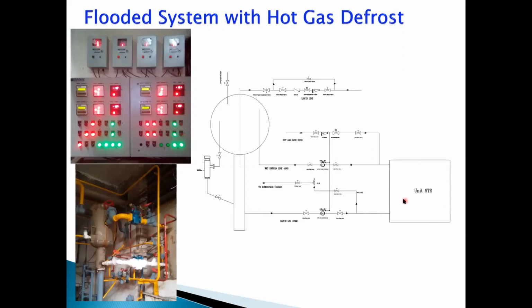The hot gas, which is coming at around 80-85 degrees, quickly melts the frost, and you can take that gas back into your system in the form of liquid. It can happen in 10 to 15 minutes. So you are not consuming any extra energy, you don't need any extra pumps, you are not wasting water, and you are saving a lot of time. That's how the hot gas defrosting system works.